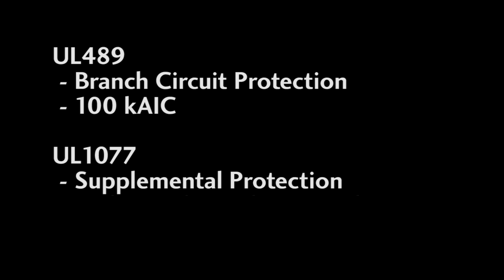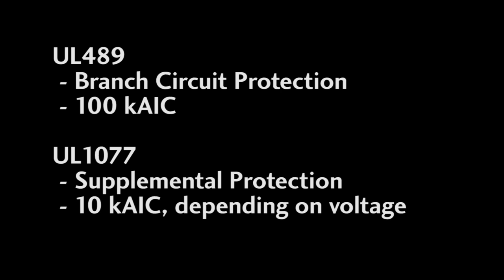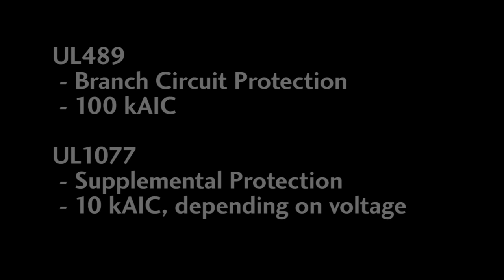The 1077 devices are strictly supplemental and should only be used where a branch circuit protection is already provided and you just want some extra protection or where protection is not required but you want to add some anyway. The 489 devices can handle up to 100,000 amps of interrupt capacity. The 1077 devices are in the tens of thousands of amp interrupt capacity depending upon what voltage you use them at.